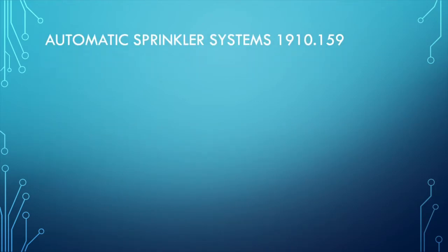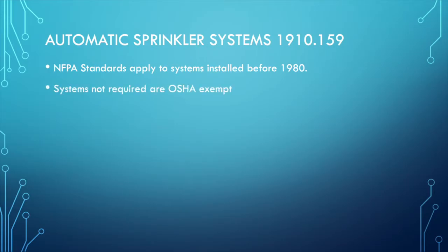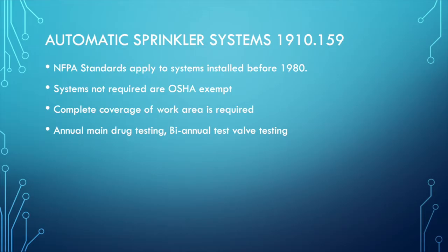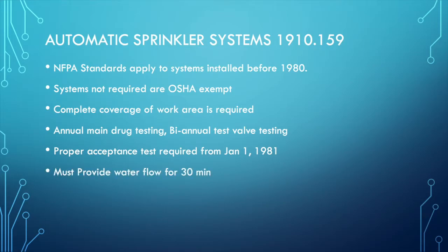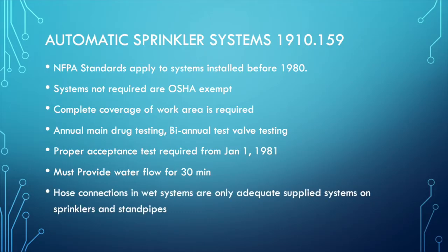Automatic sprinkler systems, 1910.159. NFPA standards apply to systems installed before 1980. Systems not required are OSHA exempt. Complete coverage of the work area is required. Annual main drain testing, biannual test valve testing. Proper acceptance tests required from January 1st, 1981. Must provide water flow for 30 minutes. Hose connections in wet systems are only adequate on supply systems for sprinklers and standpipes.